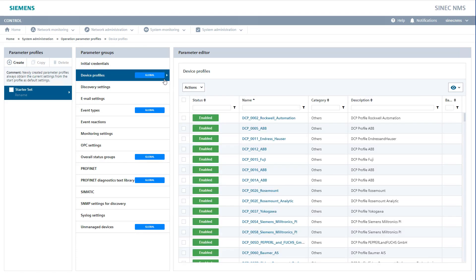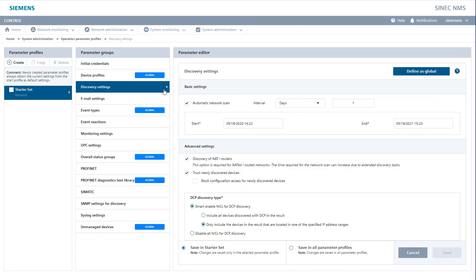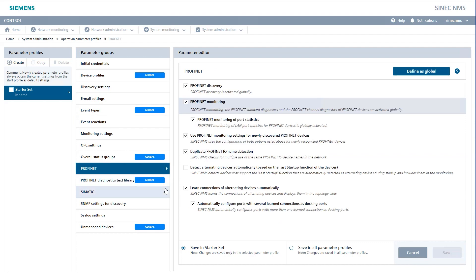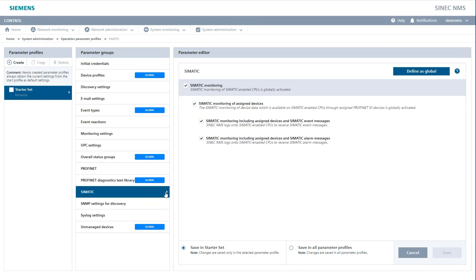At Device Profiles, we can now check whether all devices in our network are already saved in the profiles in SINEC NMS. At the Detection settings, we can now make the following settings. For example, we can specify that we want to include all devices that can be reached via DCP in the result, or only those that we select in the scan area. At the PROFINET parameters, we can decide whether we want to allow PROFINET diagnostics in the first place. Exactly the same applies to SIMATIC diagnostics.